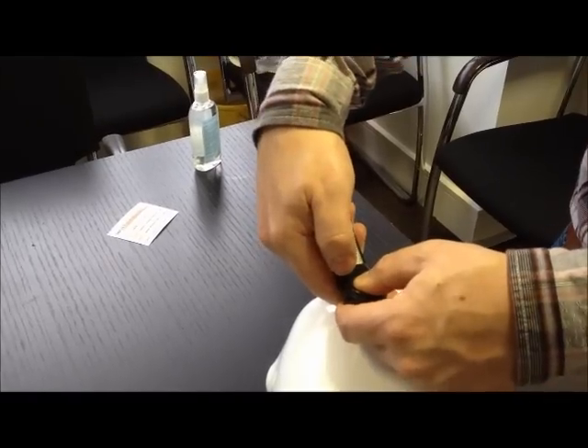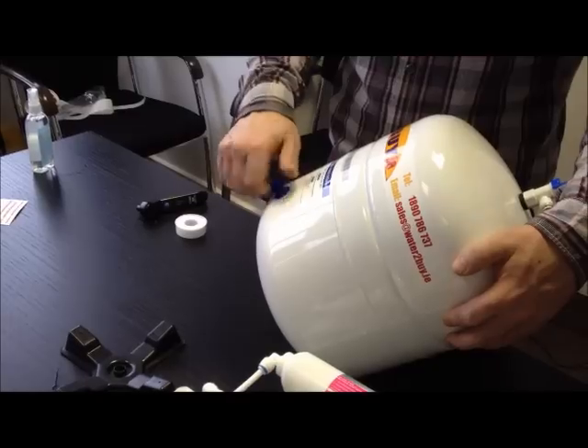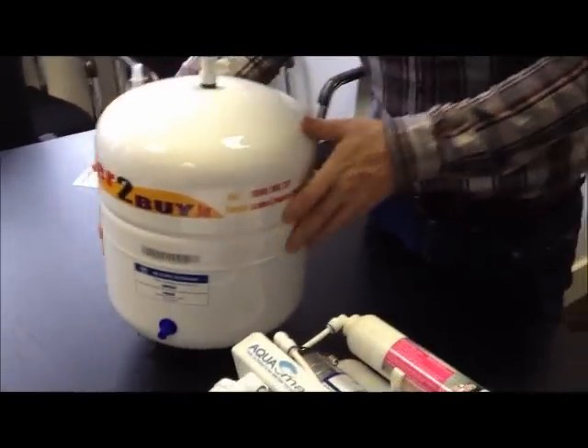If your valve does not hold pressure and continues to lose pressure, the bladder inside the vessel is damaged and you need to replace the pressure vessel.